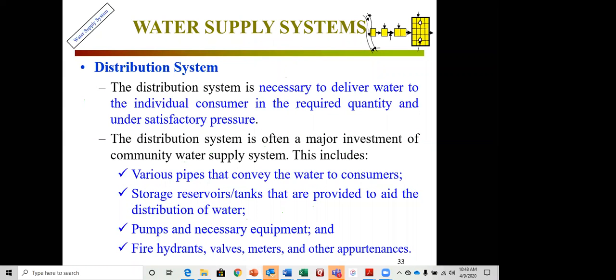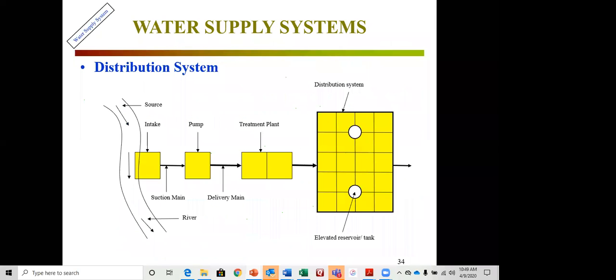The distribution system delivers water to individual consumers in the required quantity and under satisfactory pressure — typically 50–60 psi at the house. The distribution system is often the major investment in the water supply scheme. It comprises a combination of pipes conveying water to consumers, storage reservoir tanks to aid distribution, pumps and necessary equipment, fire hydrants, valves, meters, and other appurtenances.